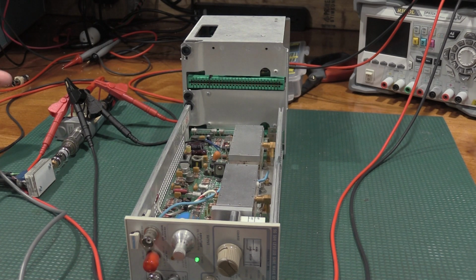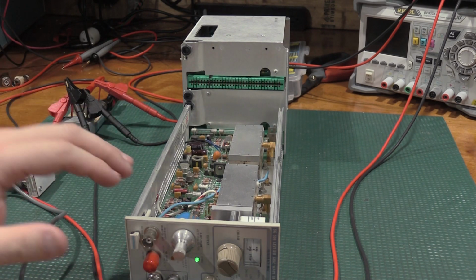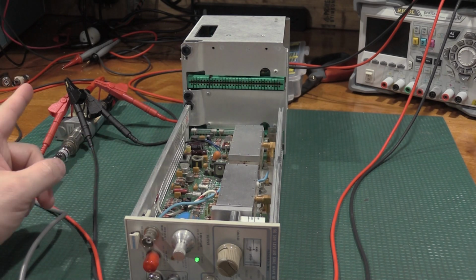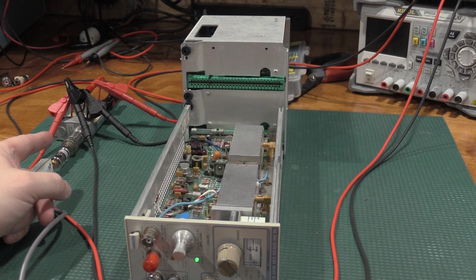Turns out my peak-to-peak detector is going to need some adjustment, so I'm going to need to figure out what that is. So I'm going to have to trust the leveling head at the moment. The good news is I've been fighting with this for a couple of hours now, and I'm getting numbers that are out of spec, but they're consistently out of spec and very close to each other.